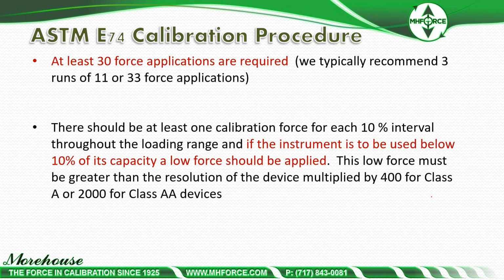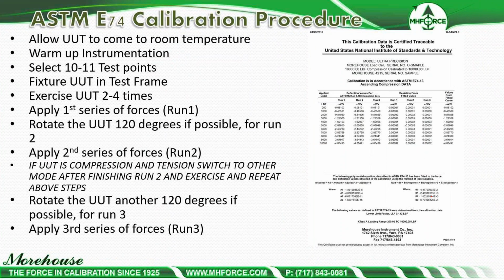That's not correct. If you take 0 and then 10%, the first point you can use in that range is going to be the 10% point. So you really can't use that device below the first non-zero calibrated point. And then there should be at least 1 calibration for each 10% interval throughout the loading range. And if the instrument is to be used below 10% of capacity, a low force should be applied. This low force must be greater than the resolution of the device multiplied by 400 for Class A or 2,000 for Class AA. If we look at the procedure, it's pretty simple.